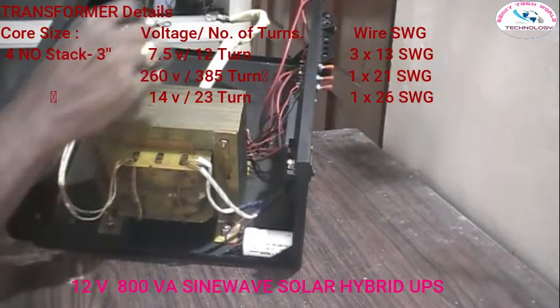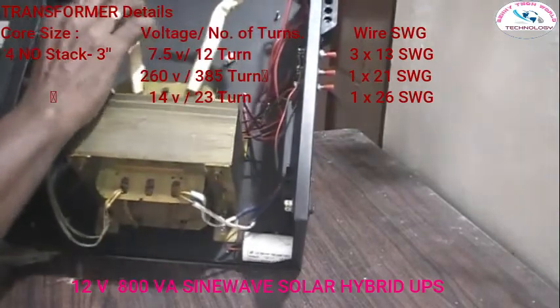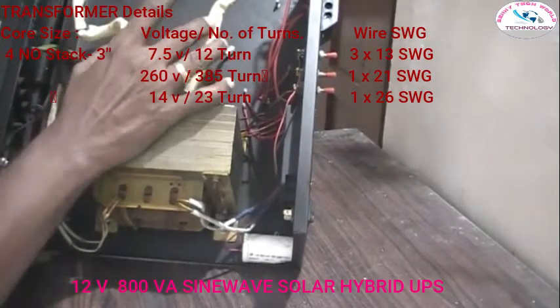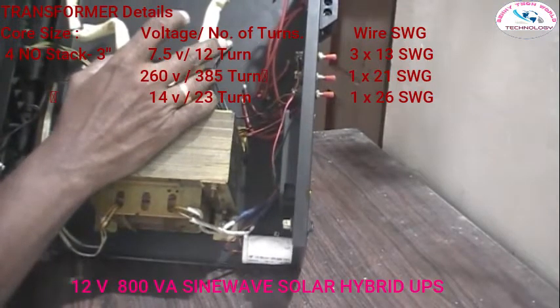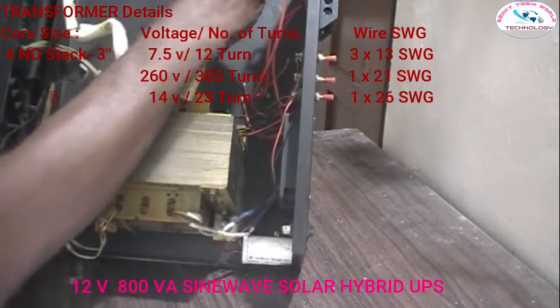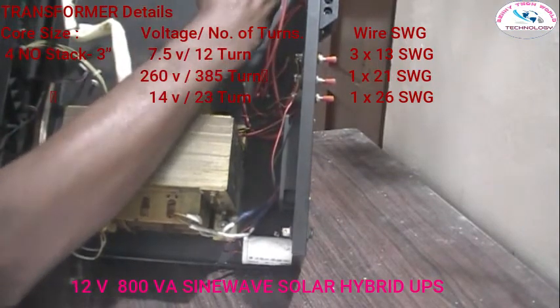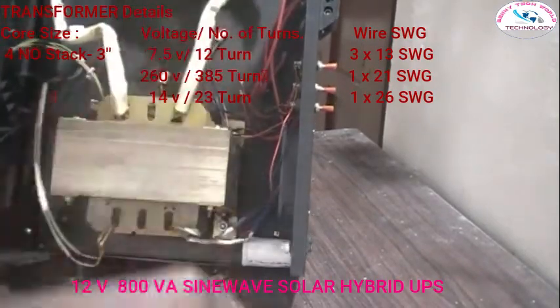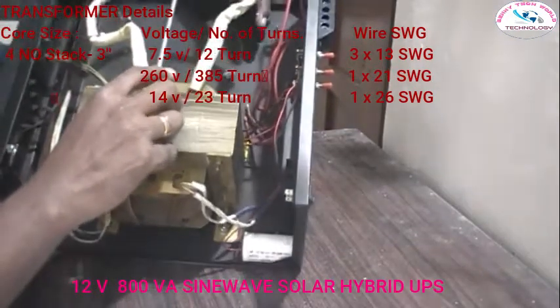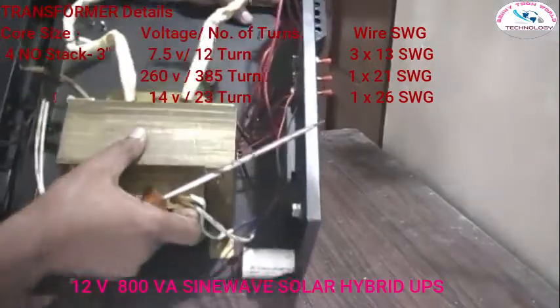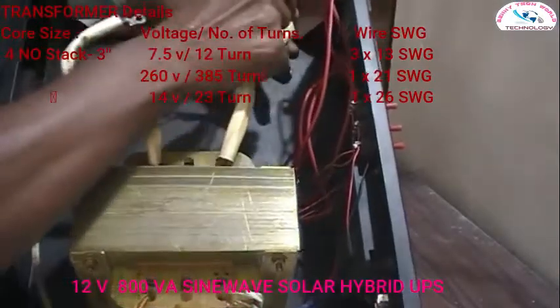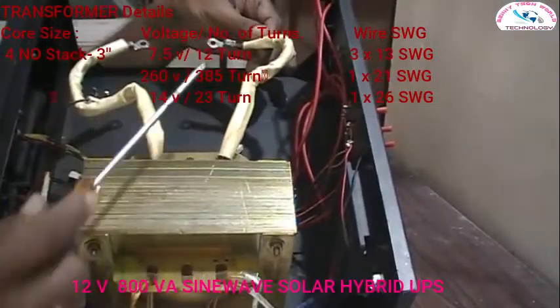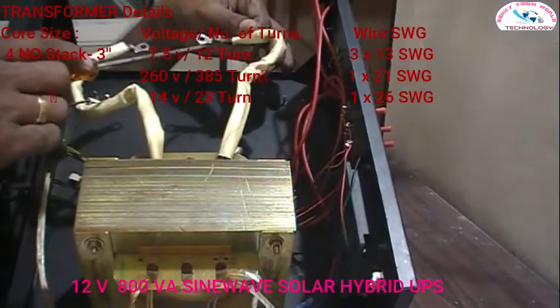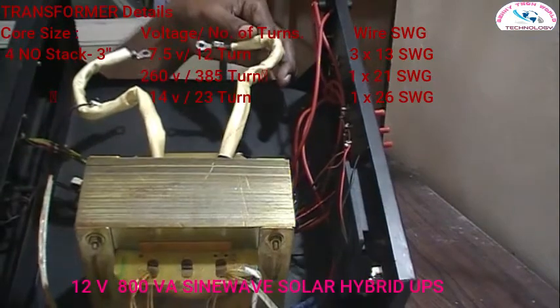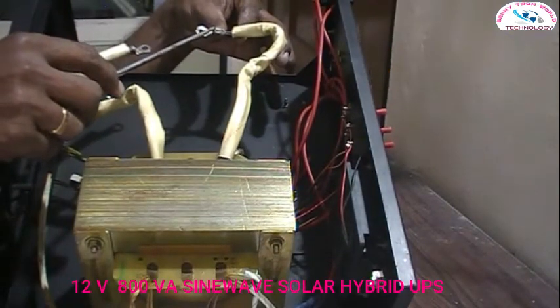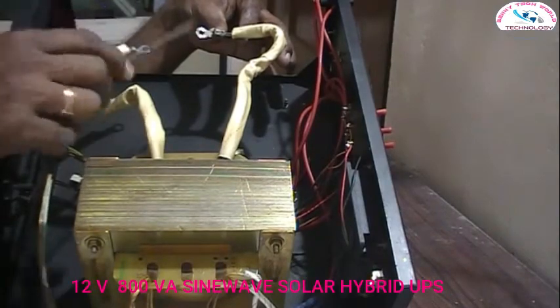The first one, 7.5 volt winding, is here - these wires are used. This is the heavy one: 7.5 volt per 12 turns, using 3 wires of 3 into 13 SWG. These 3 wires are inside the sleeve, gauge 13 SWG, voltage 7.5 volt per 12 turns. At the end of the winding wire, we provided legs for frame connection to the board.